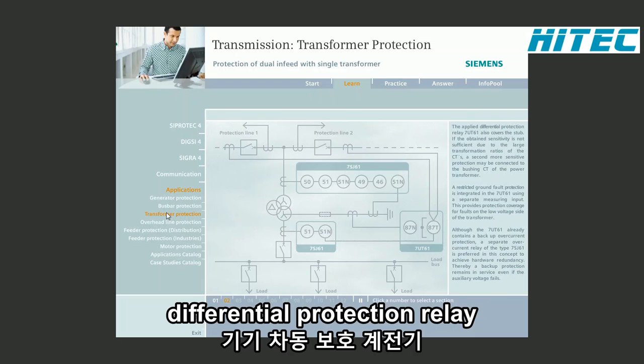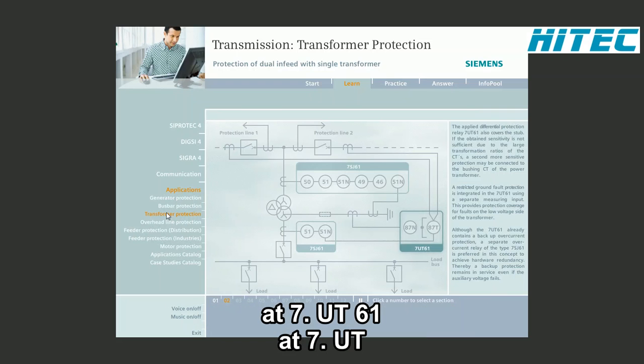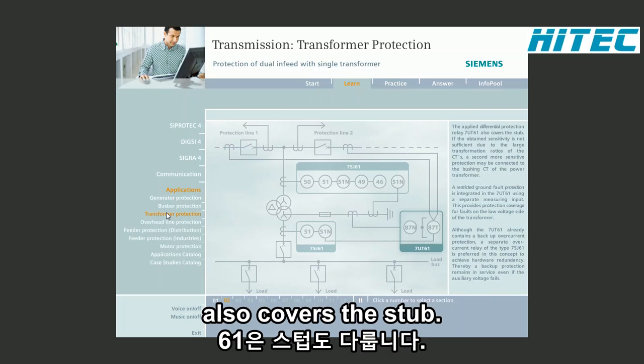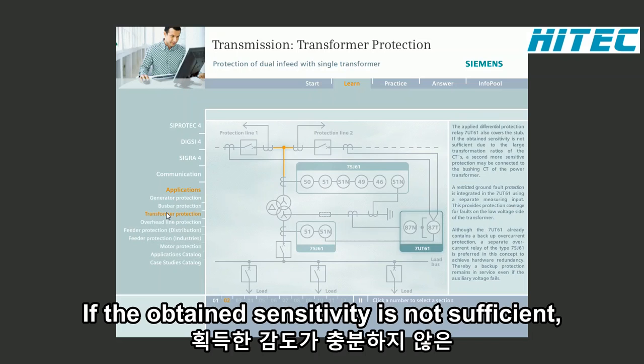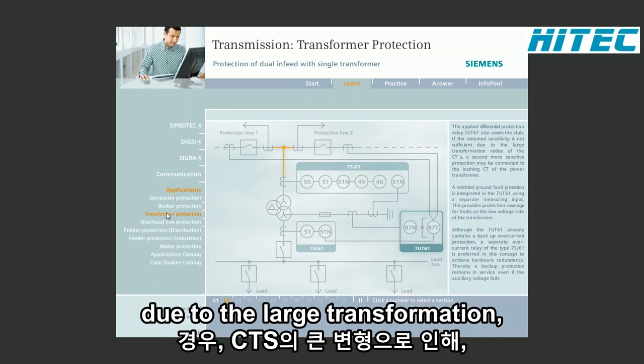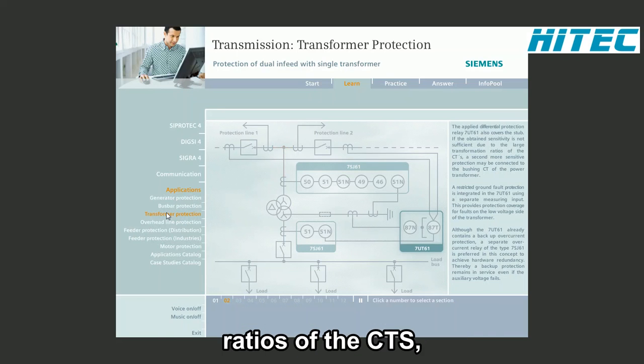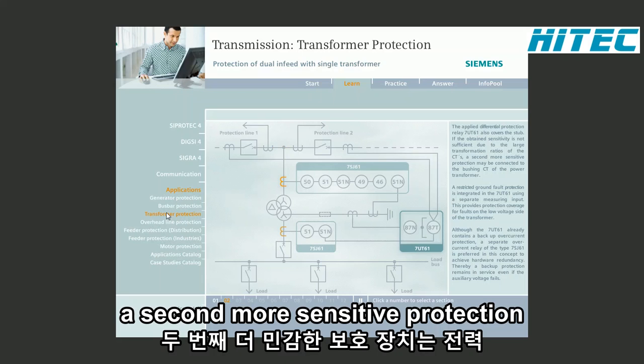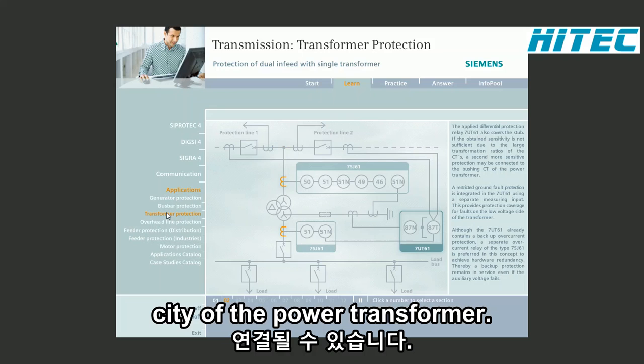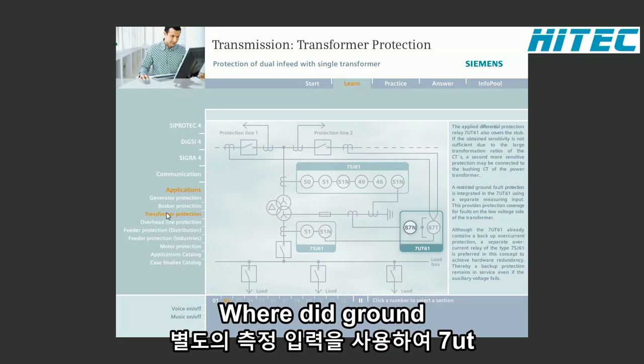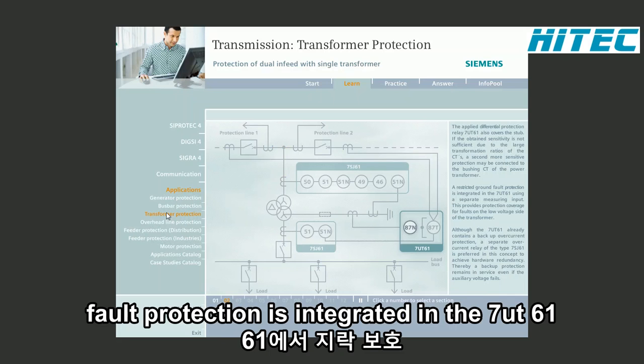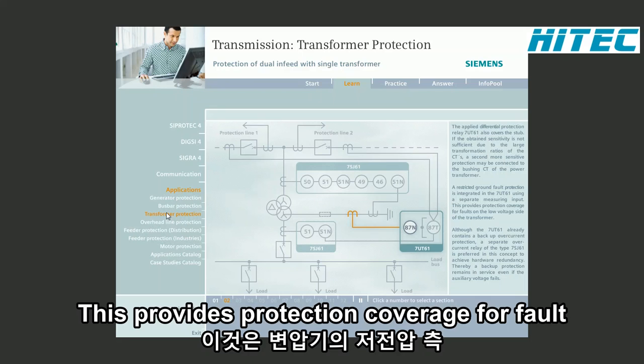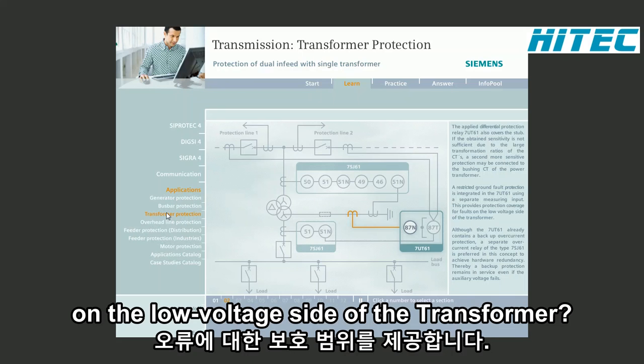The applied differential protection relay 7UT61 also covers the stub. If the obtained sensitivity is not sufficient due to the large transformation ratios of the CTs, a second, more sensitive protection may be connected to the bushing CT of the power transformer. A restricted ground fault protection is integrated in the 7UT61 using a separate measuring input. This provides protection coverage for faults on the low voltage side of the transformer.